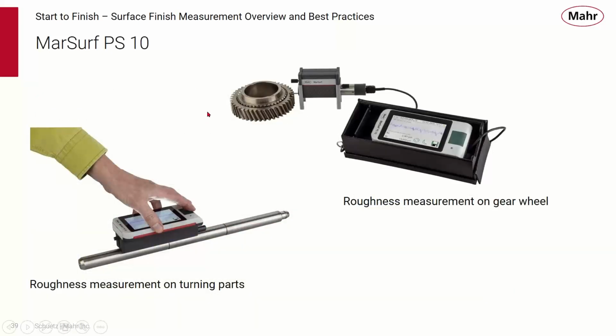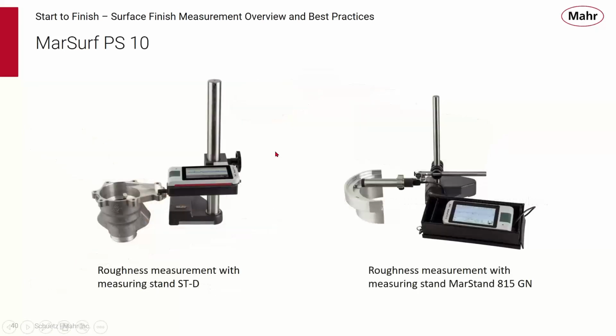remotely controlling the device to start and collect the data. So there are lots of different applications. You can use the PS10 right on the part — it has built-in V's to help align the PS10 to the part. Or you can take the drive out, mount it into this little holder, and make this a very portable roughness measurement, for example on this gear. There are different stands available for holding the whole drive and PS10 together, or you can mount the drive independently.